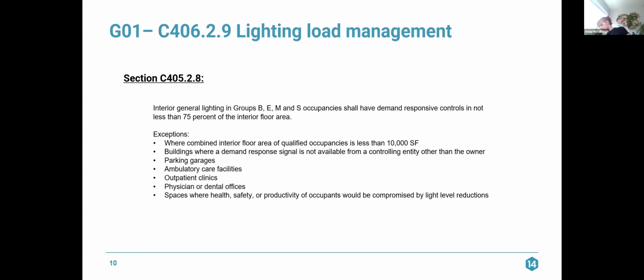Section C405.2.8, interior general lighting. This is a section that was updated by the Model Low Energy and Carbon Code and is significantly different than what's in the 2024 IECC. Interior general lighting in groups B, E, M, and S occupancies shall have demand responsive controls in not less than 75% of the interior floor area. So already, there are exceptions. Let's go through the exceptions and then we'll talk about it.